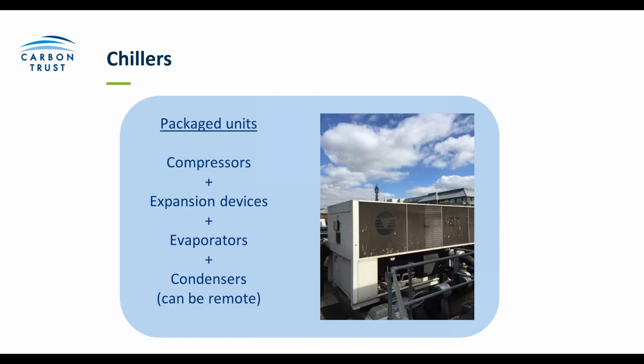Next up, you've got the chillers. So these are used in both industrial and commercial situations to produce chilled water or chill other liquids or fluids. So packaged chillers are factory assembled. They're self-contained units which include the compressor, the controls, and the evaporator. They also might include a condenser as well, but this can be a remote addition to the unit.